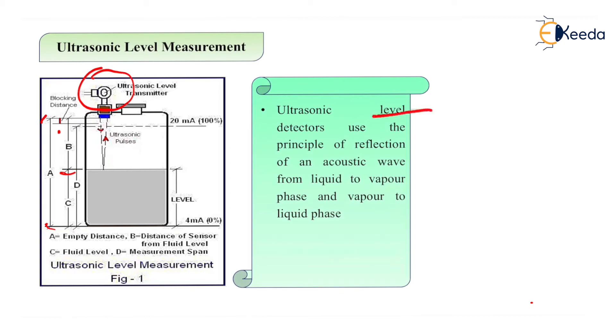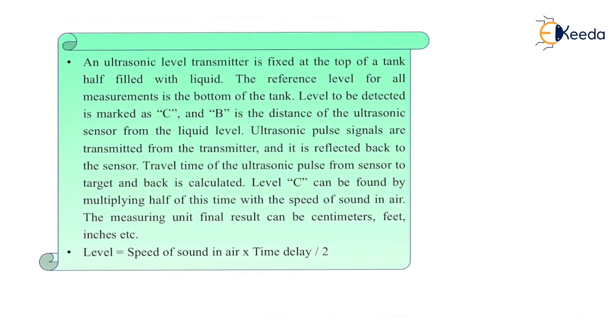Ultrasonic level detectors use the principle of reflection of acoustic waves from the liquid to vapor phase and vapor to the liquid phase. The ultrasonic level transmitter is fixed at the top of the tank, half filled with liquid. The reference level for all measurements is the bottom of the tank. The level to be detected is marked C, and B is the distance of the ultrasonic sensor from the liquid level.